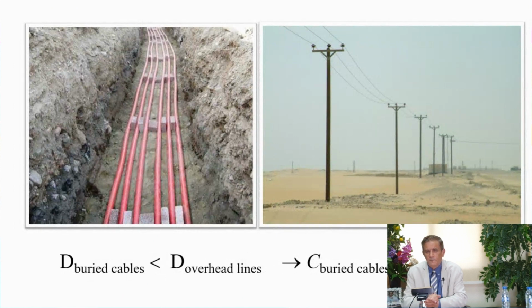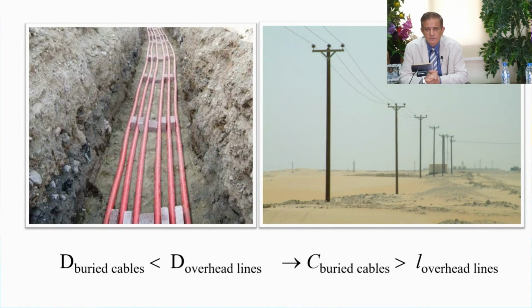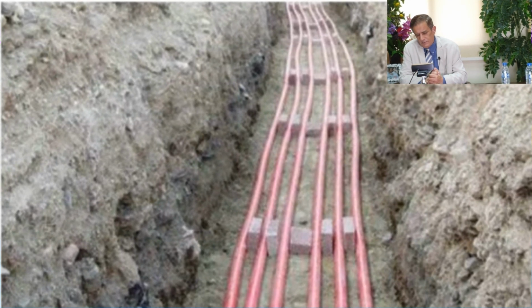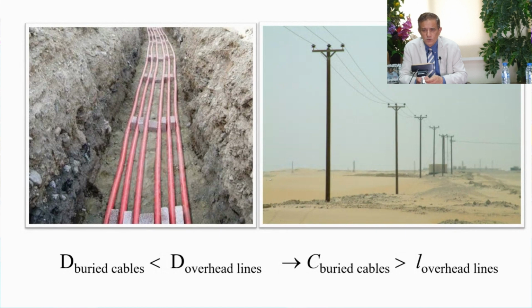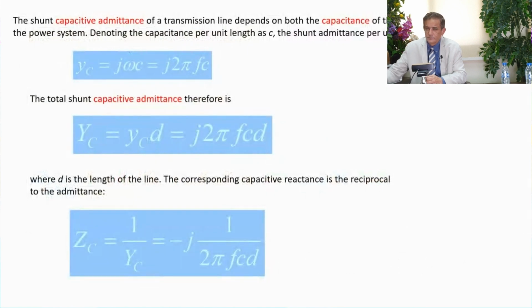This can also be shown for buried cables. When you say buried cables, it means the distance is very, very close. Sometimes the cables in the underground cable are almost touching, so the distance is very small and the capacitance is very high. That's why when we do testing or termination for the underground cable, it's crucial to discharge them even if the circuit is open, because the capacitance is very high in buried cables.